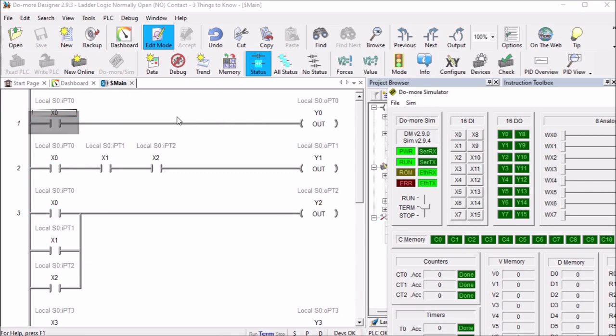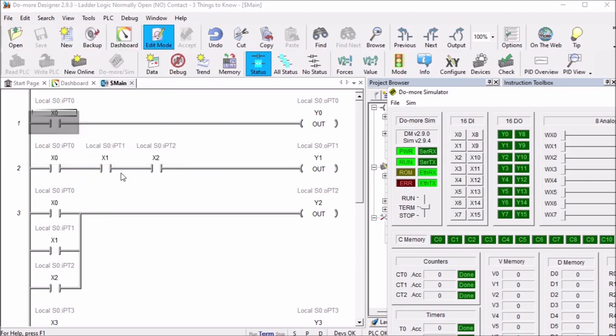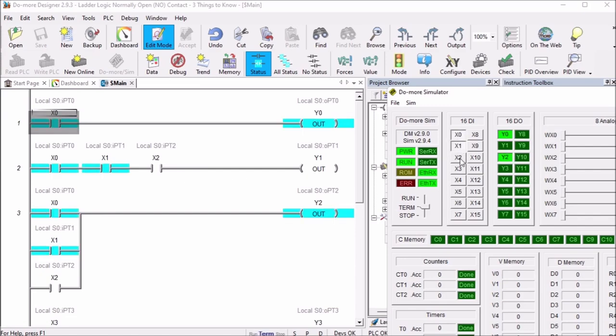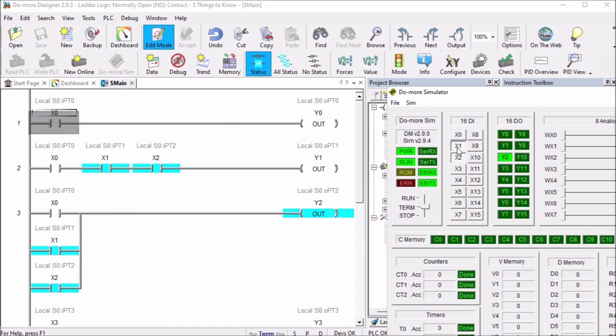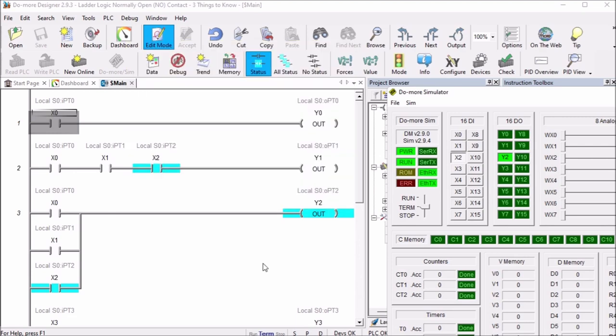We can also have normally open contacts in rungs. The inputs on the ladder can be done in series - you'll see the three in series here - so we'll need X0, 1, and 2 on and then the output will turn on Y1. Or we can do it in parallel, so any one of these on will operate the output here. So that is the first thing: ladder logic normally open contact condition.